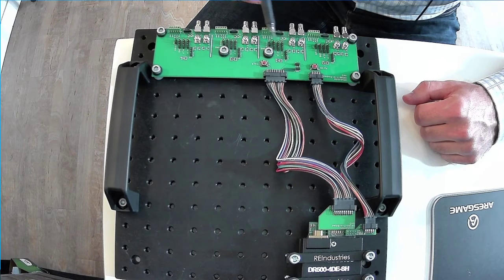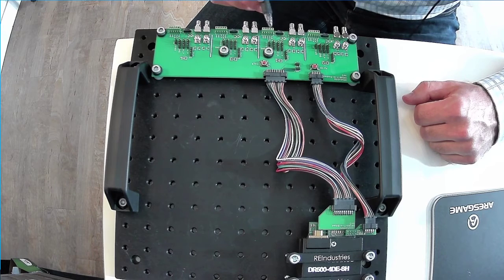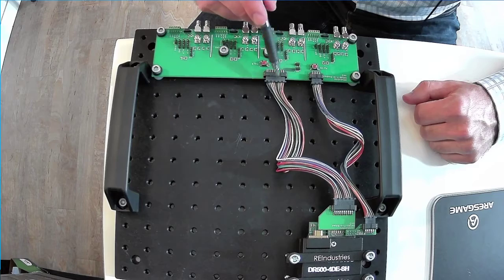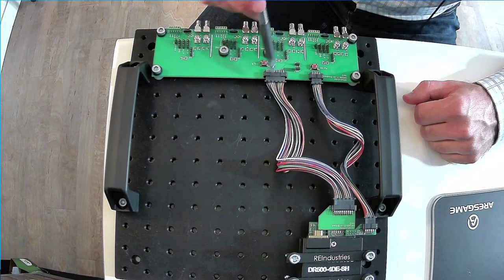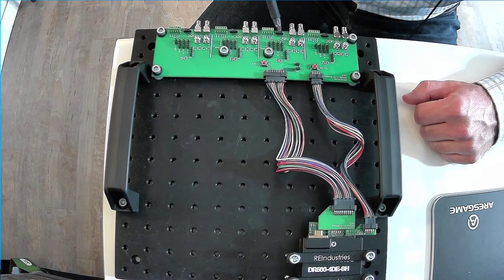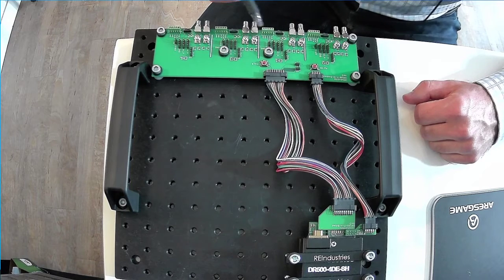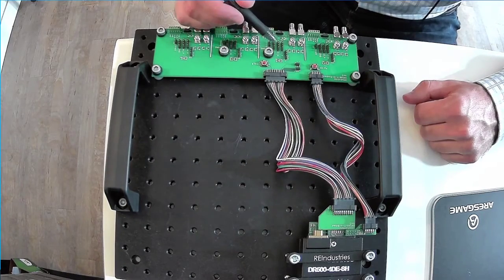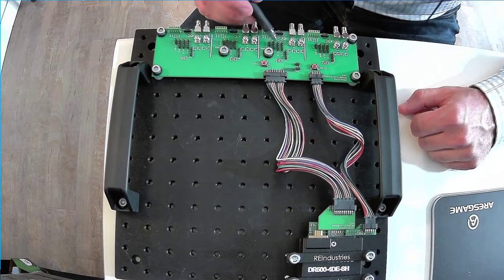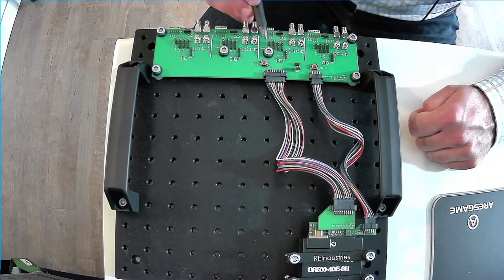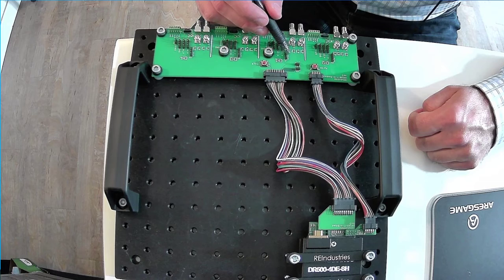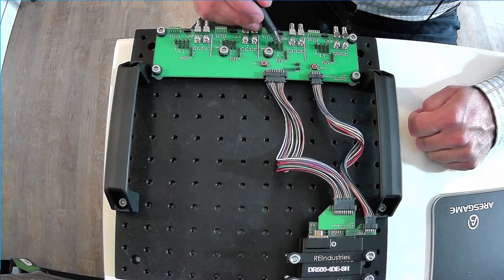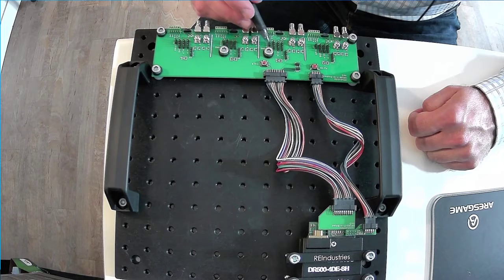This set of rectangular headers is a V bias, which is labeled VCCH. So one thing to note is that you can use the high precision voltage rail for sensor biasing that comes out of the unit. It is a VCCH. And so these V bias signals actually are the unit's high precision voltage rail. So when I say excitation voltage or VCCH, for this platform, it's generally intended to be the biasing voltage from the actual data recorder. This data recorder line can bias the sensors directly. If that's not intended, you don't have to use that. But that's generally, it's pretty common. So that's built into this design. So for the rectangular headers, we've got VCCH, high precision voltage rail for excitation voltage sensor biasing. The two accelerometer signals, P and N differential signals, a ground, and then a shield.